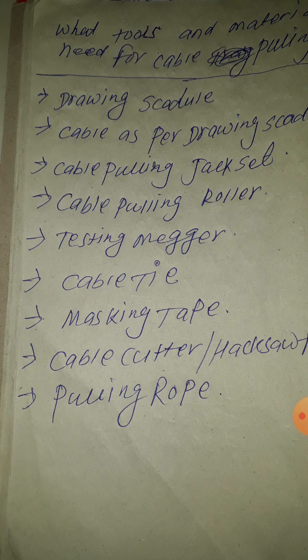in marking time. After finishing the cable, on both sides you should mark with masking tape, and write the cable number on the masking tape as per your drawing schedule. Both sides, first side and last side, you write the same number. Because the cable has two parts, starting part and ending part, you put the same number on the starting part and on the ending part. So this is easy for identifying the cable. Properly put the masking tape there, and put plastic tape also to cover it. Don't remove the numbering. So that time you need masking tape also.